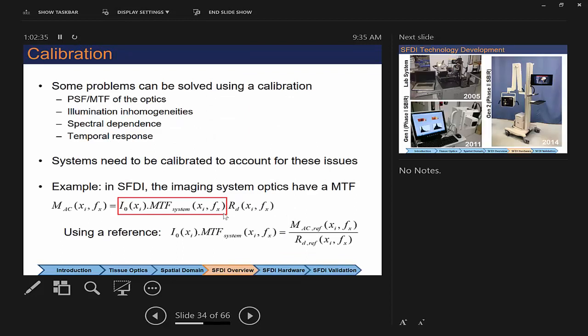Okay, so calibration is a huge topic. We've created these tools that you've started to use in the virtual photonics simulators, and one of the big things that's not addressed with those tools is the fact that in real life you've got real world systems with noise, with spatial dependence, with time dependence. You have the MTF, modulation transfer function, of your system, and you've got to come up with some way of correcting for it, or knowing what it is, or comparing your measurements to other standards, like you can have arrays of phantoms. You've got to figure out ways to make sure that if you're fitting reflectance, that it actually is reflectance. Reflectance should be a unitless number from 0 to 1 that is telling you in an absolute sense, if I send in 1 unit of light, or a billion photons, how many of those billion will reflect as a fraction.